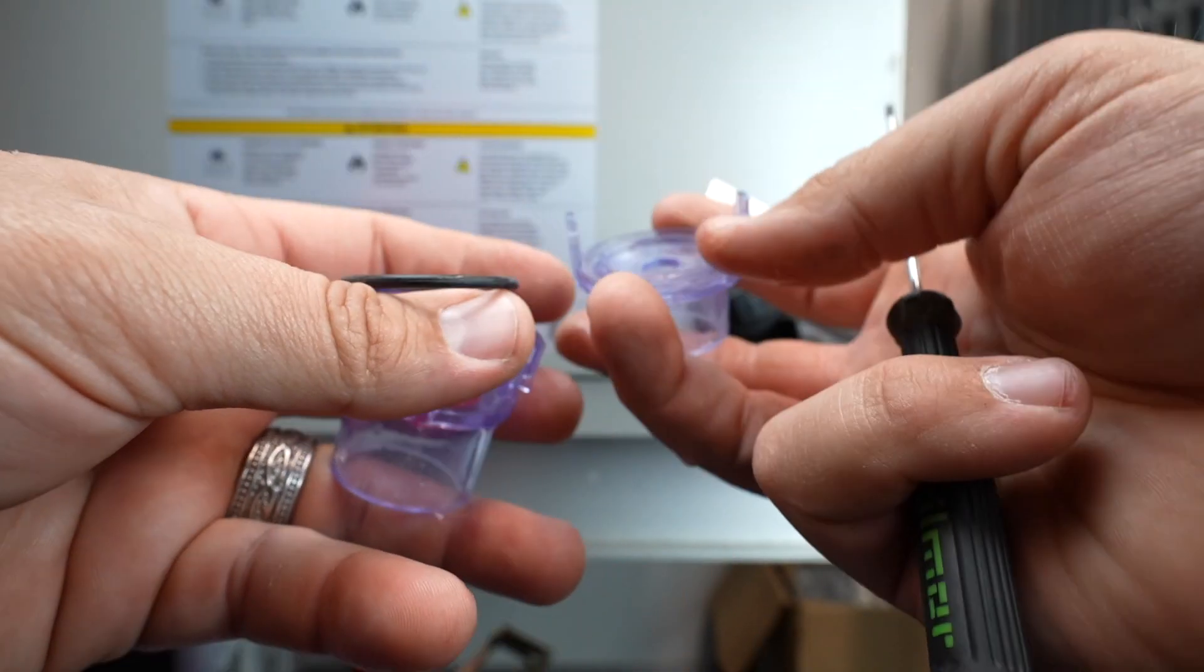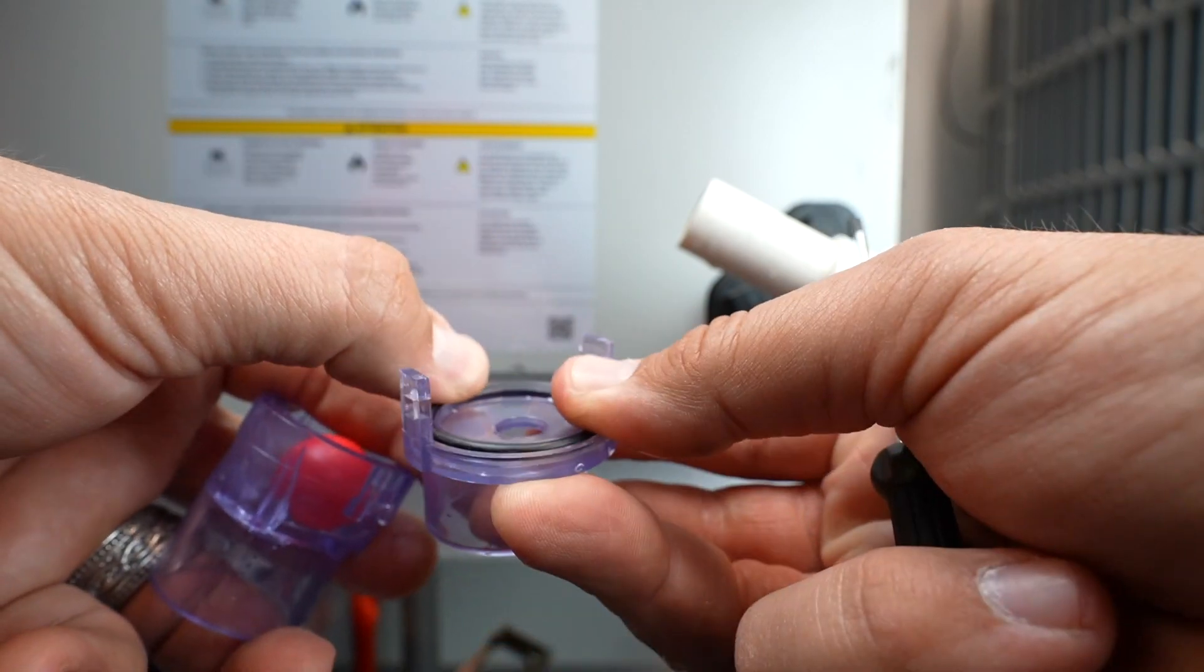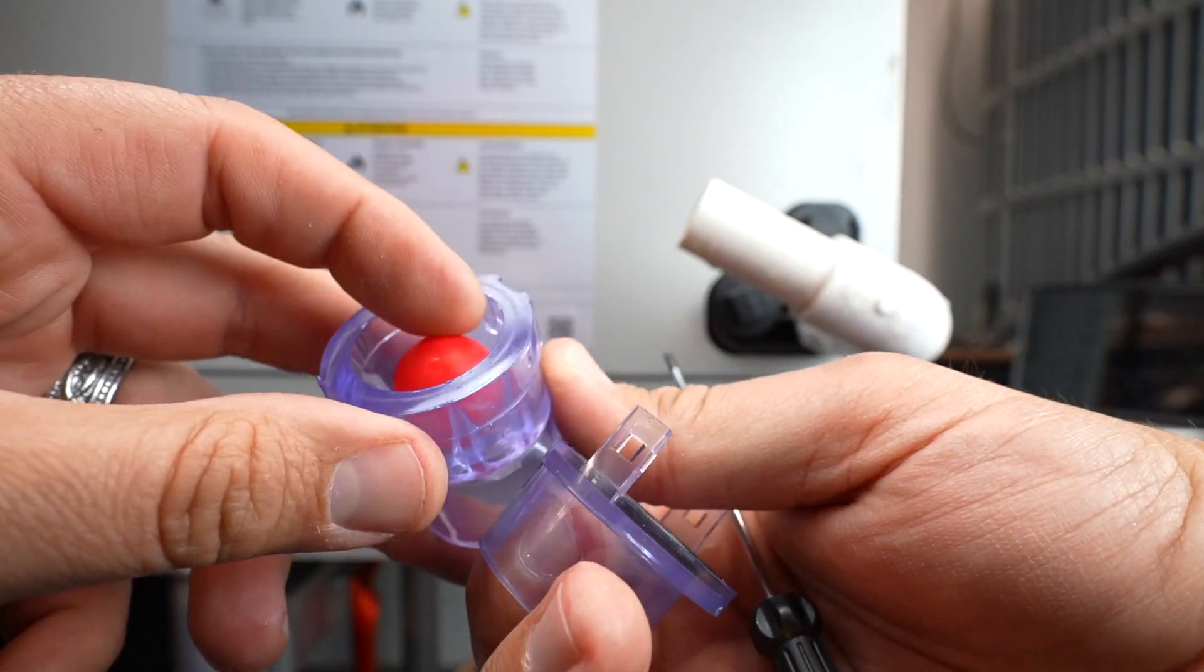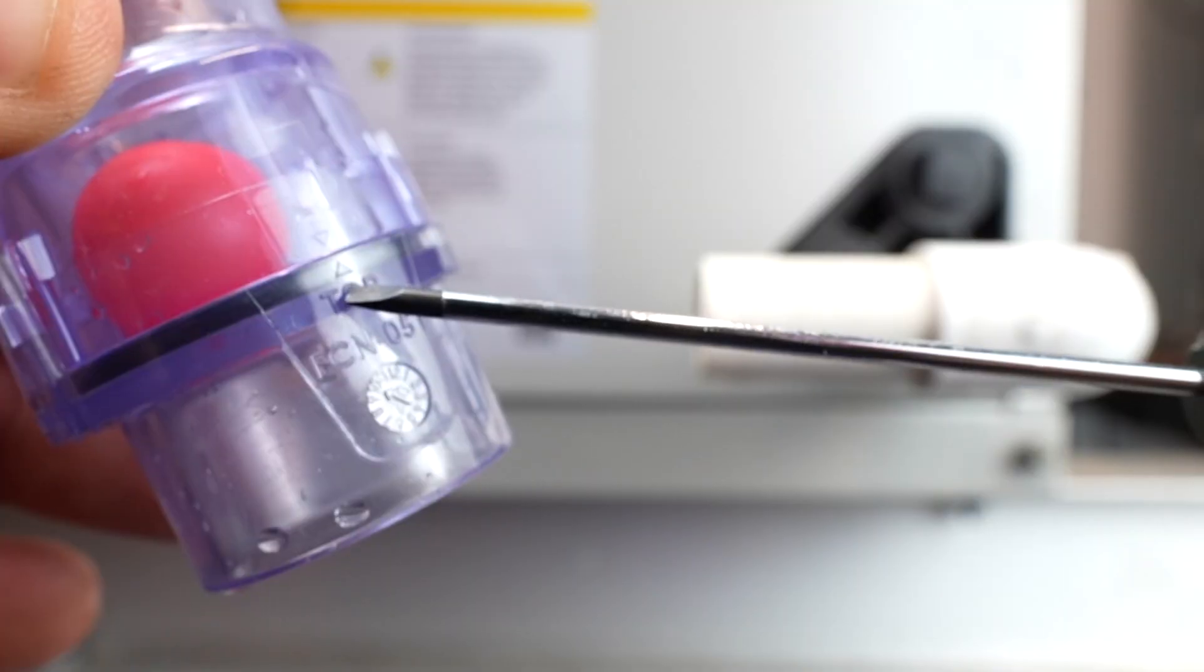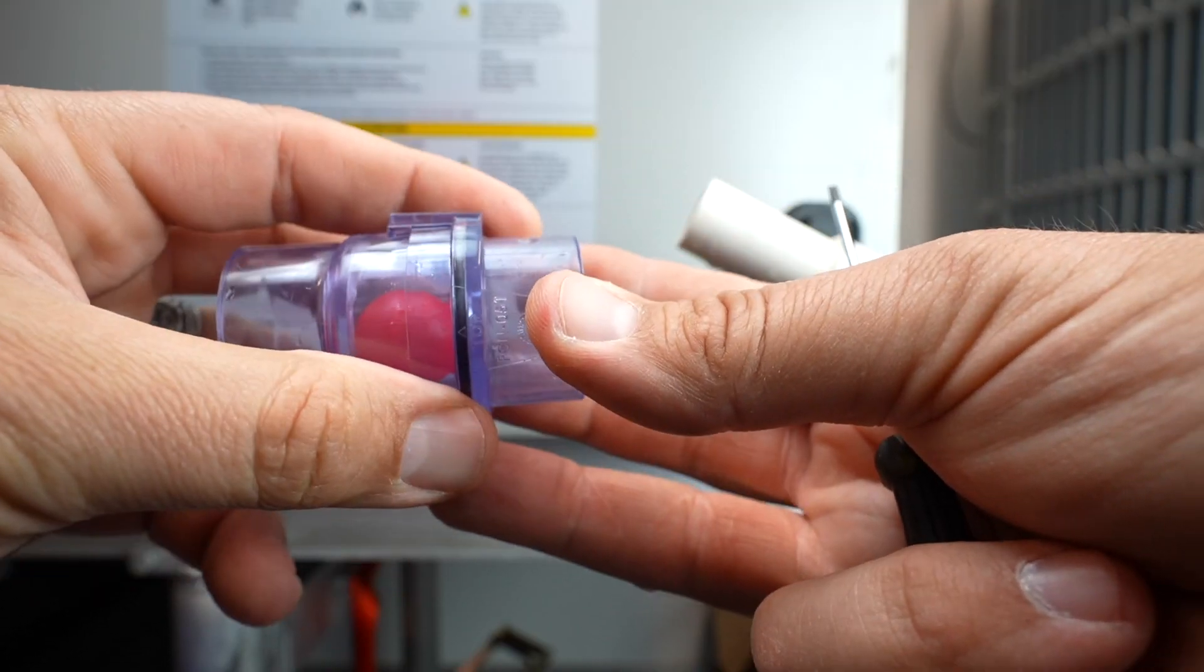When inspection and cleaning are complete, reassemble by installing the O-Ring in the groove. Make sure the ball valve is positioned properly, line up the side tabs, verify the arrows on top are lined up, clip together, and you're all done.